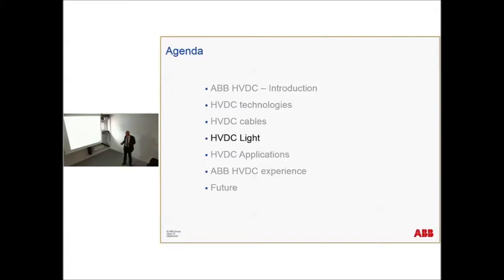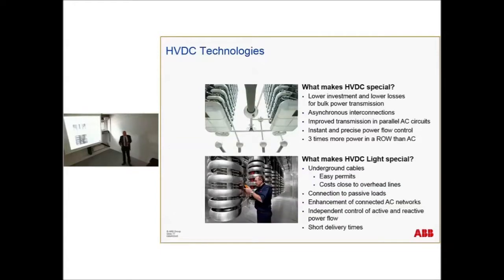So if we make a short repetition, we say HVDC is special for low losses, long power transmissions, overhead lines or submarine cables. Can connect asynchronous networks, have a precise power flow control. Thereby we can increase the stability in an existing network by adding parallel DC links. And this is what we call line commutated technology with the HVDC classic.